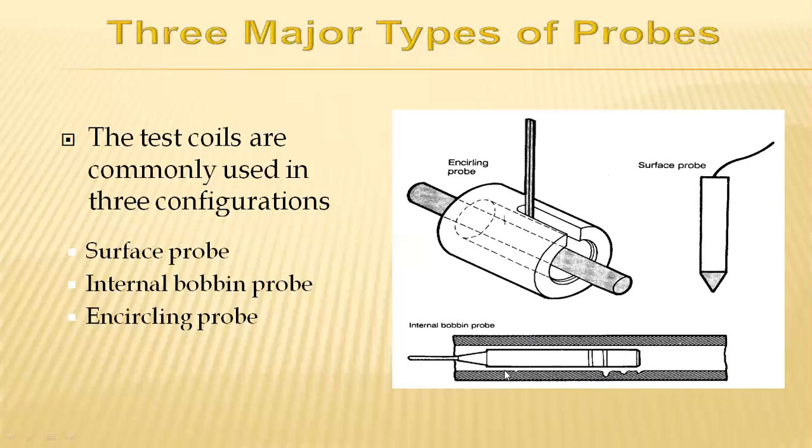The normal thickness of the internal bore diameter and outer bore diameter will be specified, and the thickness needs to be similar everywhere. Where variance occurs will be clearly examined, and how much depth of penetration exists. The geometrical specifications of identified cracks or destruction of the laminate position can be identified very clearly in the case of slotting actions or internal bore actions.